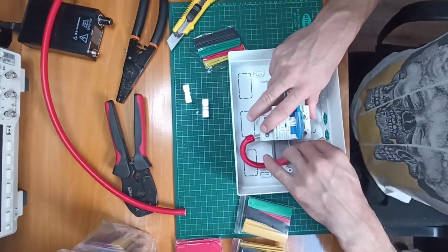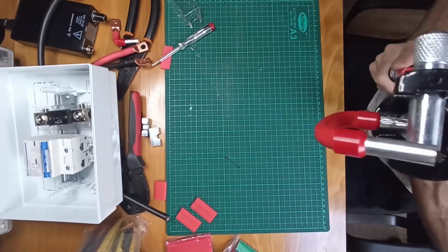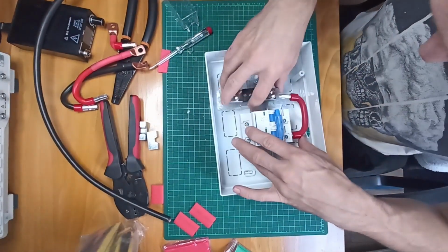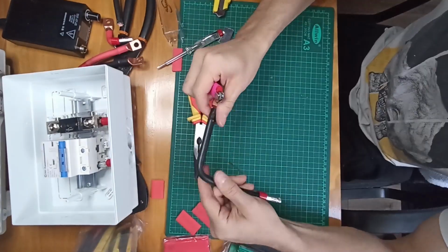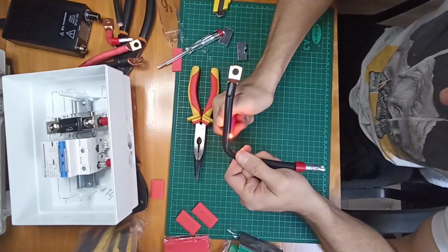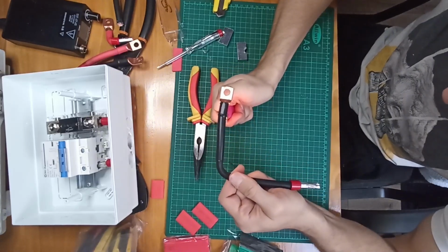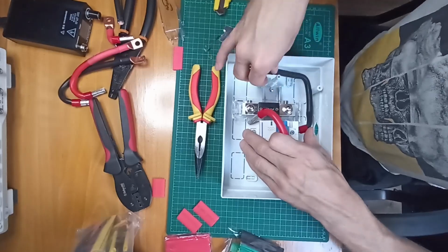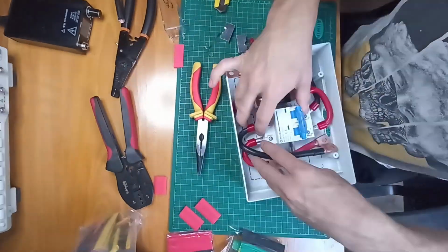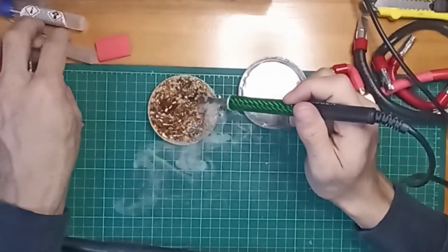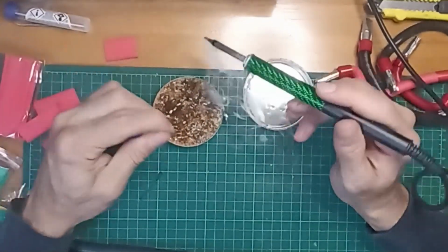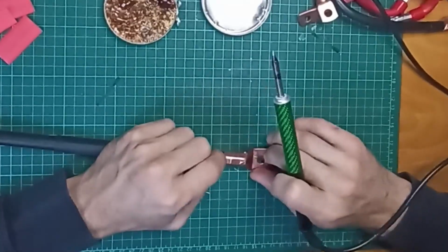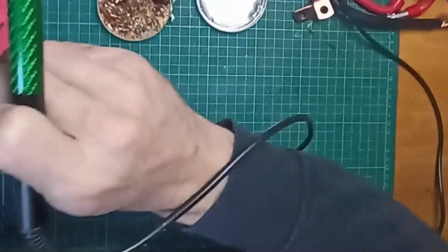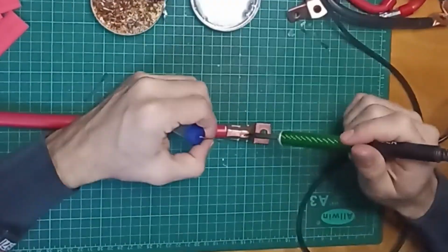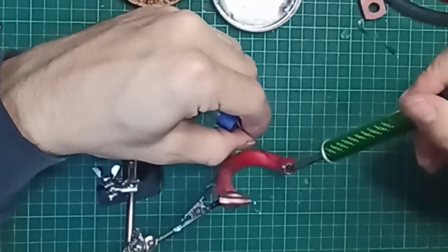In a 48 volts power storage, I have got 16 of those. In the moment of short circuit, that's basically a welder. It will melt everything instantly. First insulation, then after reaching thousands of degrees, even thick copper wires. A kindly reminder though, auto-ignition can happen after reaching just 300 degrees Celsius. To answer the unspoken question, yes, this is the main reason why solar installations catch fire. So please, it's no joke. You need to be very careful with such high power batteries.